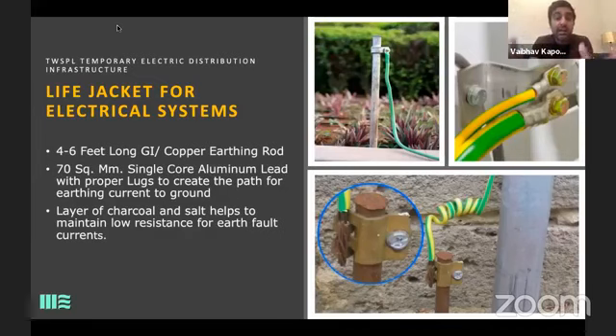Why? Because the connection from the rod to the wire has to be proper. Why are we using a 70 square mm, which I've mentioned, a 70 square mm single core aluminum lead with proper lugs? Because ultimately, if something goes wrong, this wire is taking it to the ground. If you're using a small wire, and it can't take the load of the unwanted current which is flowing in your phases, then ultimately that earthing wire will also burn, and you will be at the receiving end of that shock.